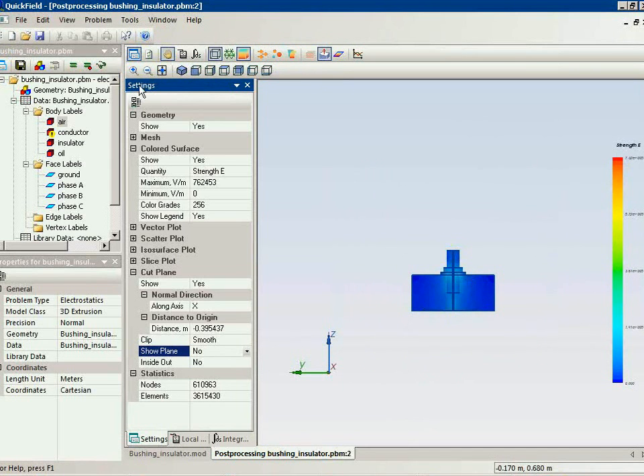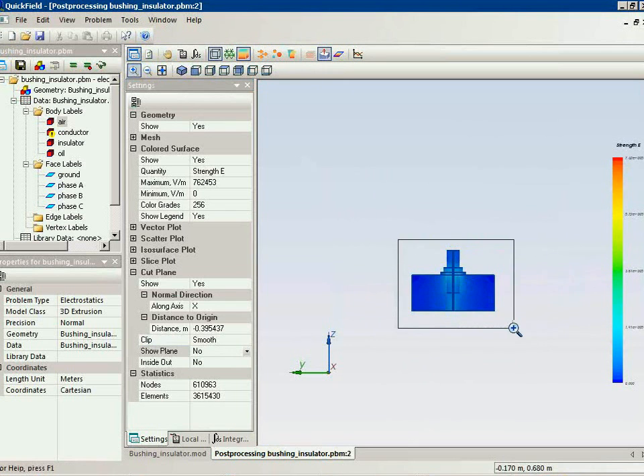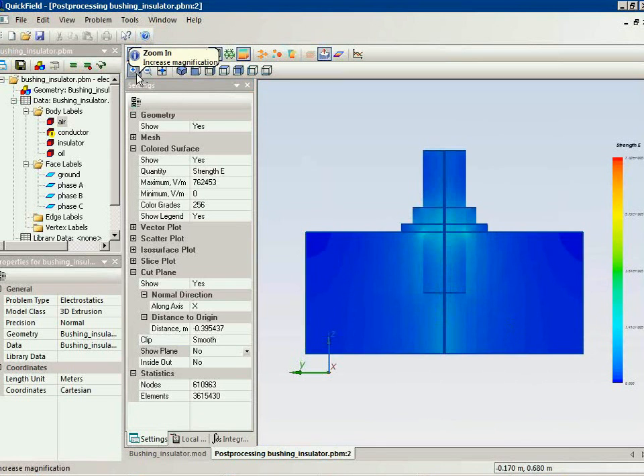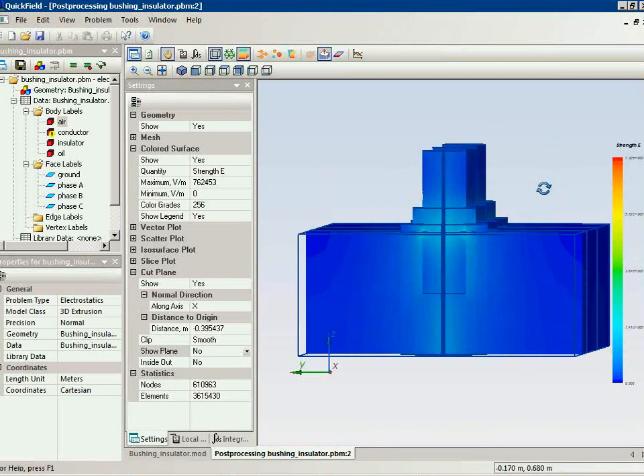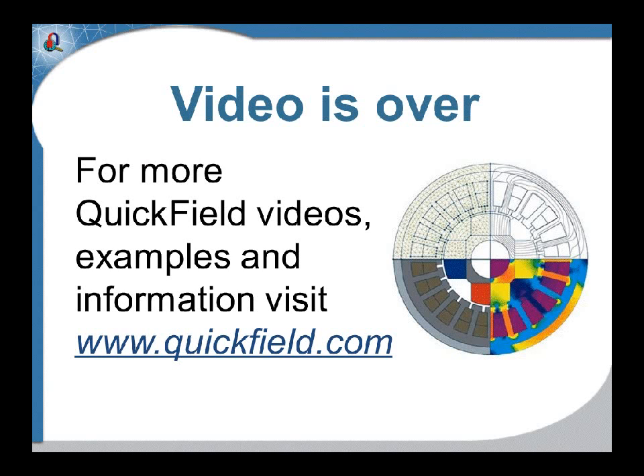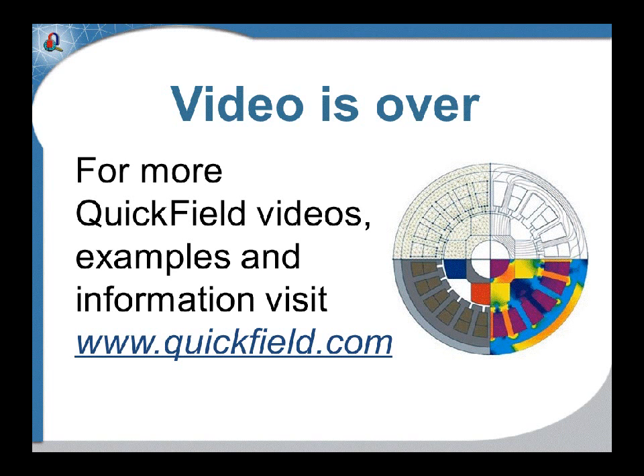Now this is what we get inside the A-phase insulator. The electric field stress distribution inside the A-phase insulator.